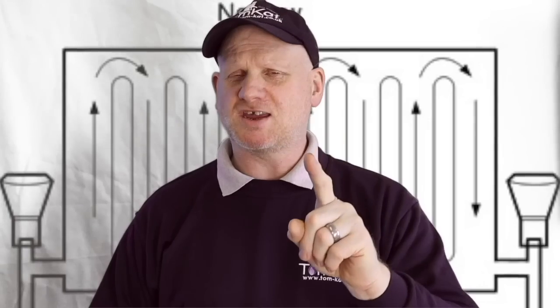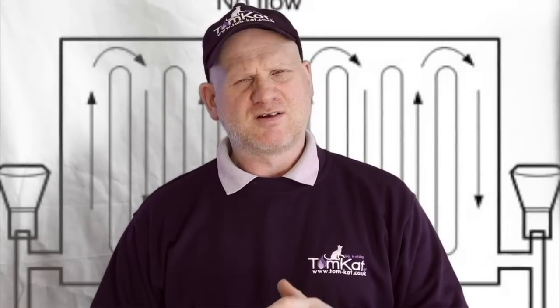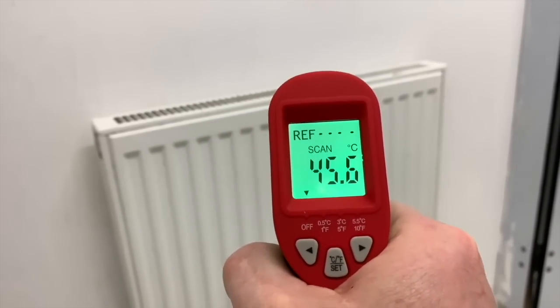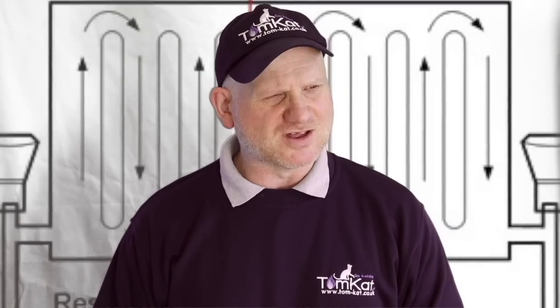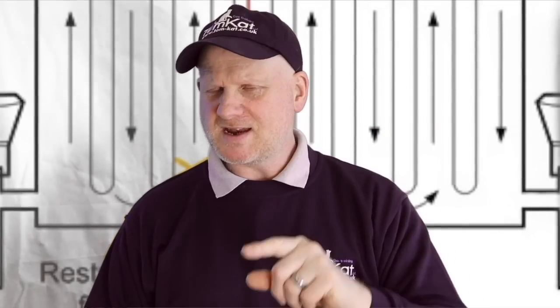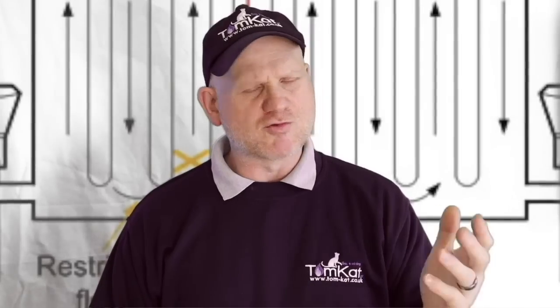Number two: check whether the radiators are warm at the top but cold at the bottom, or completely cold. You could also use an infrared thermometer to test for cold spots. Number three: ask the customer whether the rooms are not getting hot even with the thermostats fully open. Number four: ask whether they are bleeding radiators all the time, because what they'll be bleeding out is hydrogen — a byproduct of corrosion in the central heating system. Number five: carry out a water sample test.